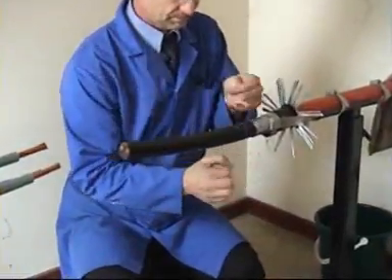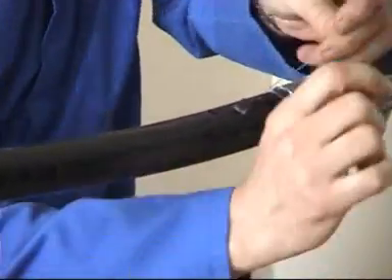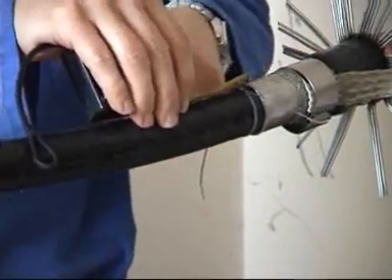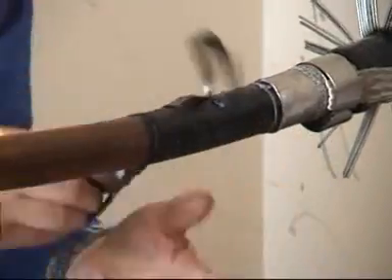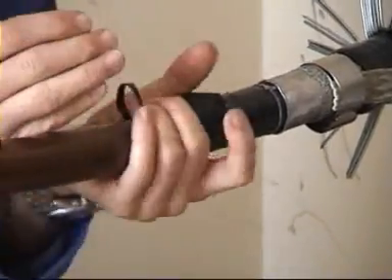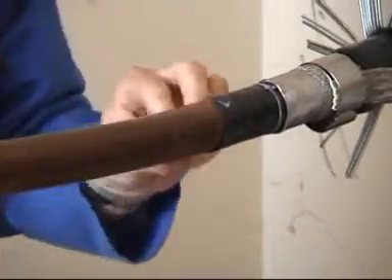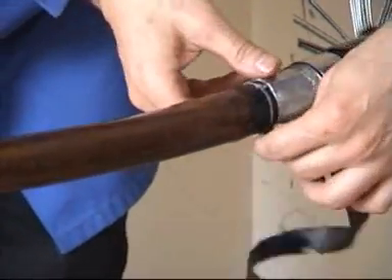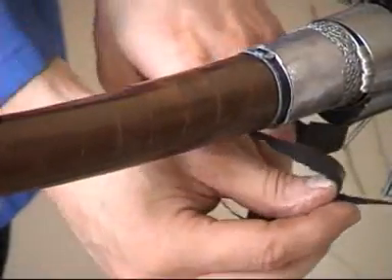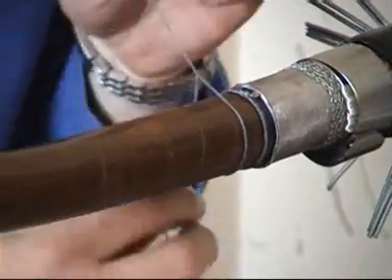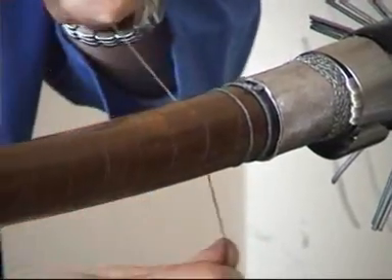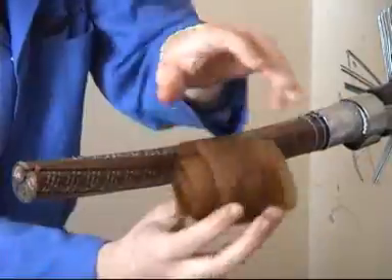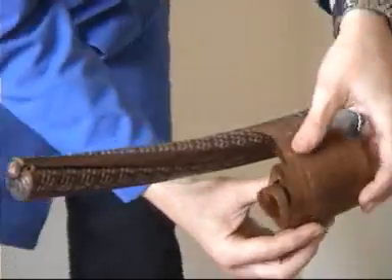We now need to expose the carbon belt papers to a point 5mm beyond the lead sheath cut. Tie a twine binder and unravel the carbon belt paper to this point. A further binder should be applied 20mm beyond the carbon belt papers, then the remaining belt papers removed to this point.